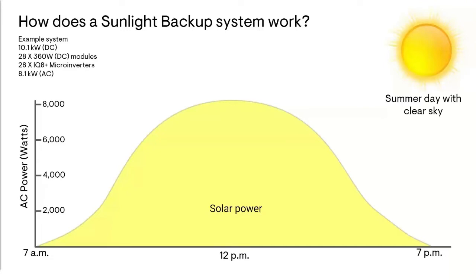Before that, I wanted to talk about a very common misconception out there, that inverters are going to deliver their full rated power, meaning their power rating on their spec sheet, whenever the sun shines. But this isn't the case in the real world. The actual power output of a solar inverter is relative to the irradiance, or the intensity of the sunshine, as well as the specs of the solar module itself.